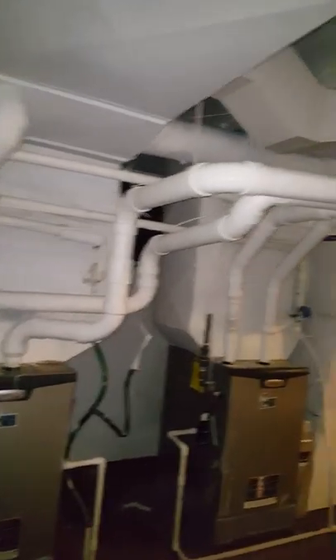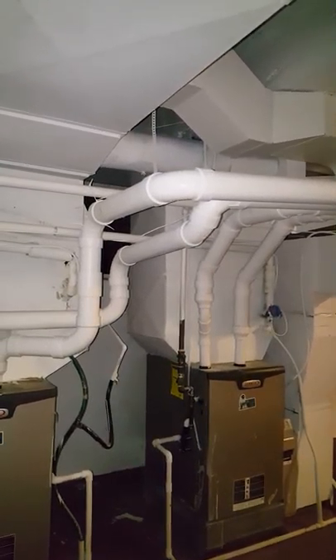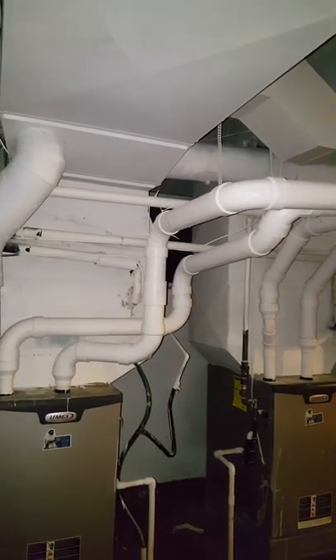The pipe above that window is where they go out and the AC unit is sitting right out there. We do have an inch and an eighth by three-eighths line set on a five-ton unit, so we can flush it out or we can replace it. I'll put a note on there about what we're planning on doing.